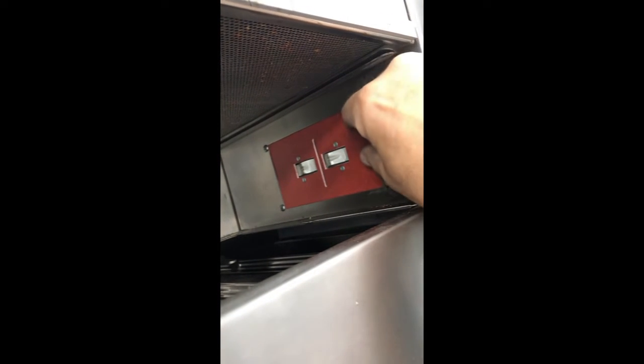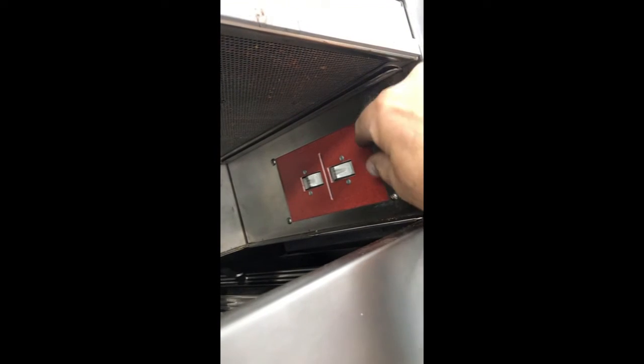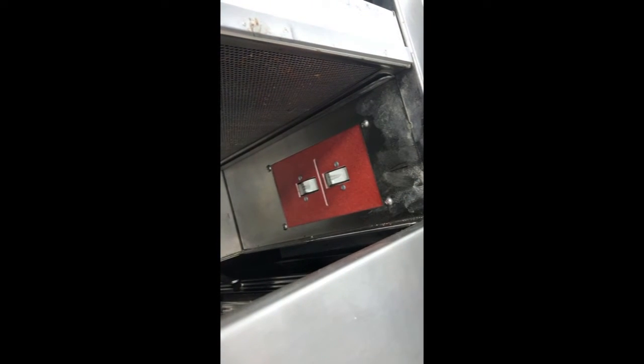Now for those times when just cleaning the EAC filter, everything ohmed out okay and you're still having problems, check these contacts here and make sure that when you slide the filter in here, you're making a good connection. And also make sure that the lever of this is not landing on one of the rivets on those contacts. We don't want to ride the rivets, we want to go straight to the copper. If that's a problem, you take these screws out and you can pull this plate, they go into a little plate in the back. Pull these screws out, take this plate out and just elongate the holes a little bit so you can raise it up or down as needed to try to get it to line up so that it's just on the copper.